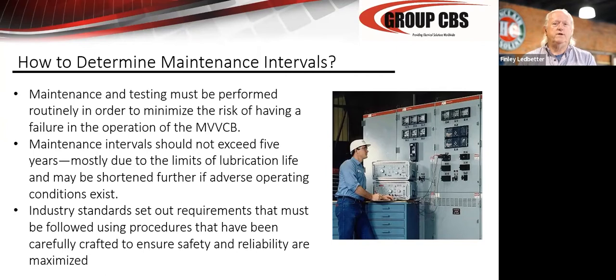You know, you're talking about shipping the breaker. If it's an older breaker that doesn't have spline protection, the newer breakers all have splines built into the contact assemblies and the moving side so that they won't twist, turn, or vibrate, so you don't essentially wear the bellows like the older ones. The older breakers that were built, say, in the 70s, 80s, even into the 90s, the problem with shipping the breaker open is that the bellows vibrates at a high frequency the whole time it's driving down the road. And the bellows is only a few mils thick of stainless steel, and it can't stand that.